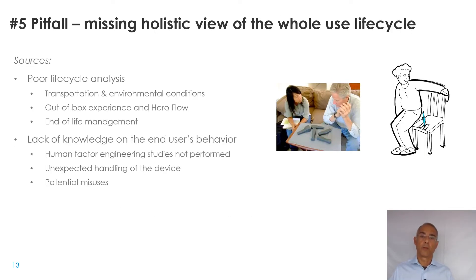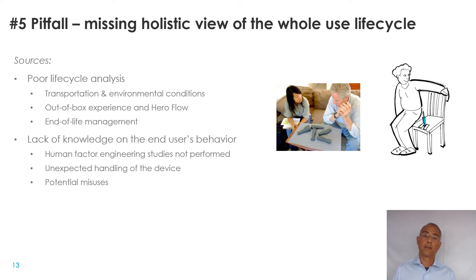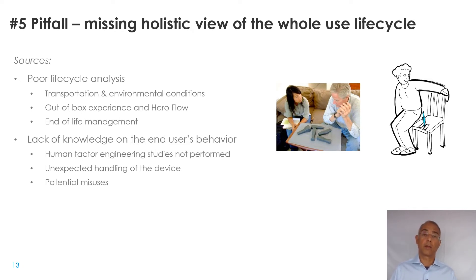Pitfall number five: not having a holistic approach across the entire device lifecycle. You need to consider what happens during transportation under severe environmental conditions, and at end of life where the device is discarded and recyclability and waste management must be addressed. Another key point is focusing on the end user — understanding exactly what they plan to do with the device in specific conditions, typical user behaviors, potential misuses, and planning for all of that in the device features.